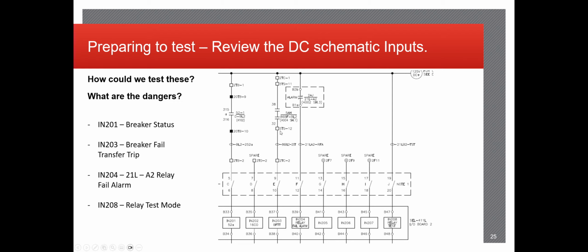Relay test mode. This isn't something that I went over earlier, but I can mention it now, especially prominent with the GE relays. A lot of times when you're testing those, the relay won't even allow you to change any of the logic in it, meaning you can't set a spare output to whatever relay element you're testing, or even change some of the logic itself, unless you put the relay in test mode specifically. Test mode pretty much means it's going to operate certain stuff, but it's not going to send any direct outputs unless necessary.